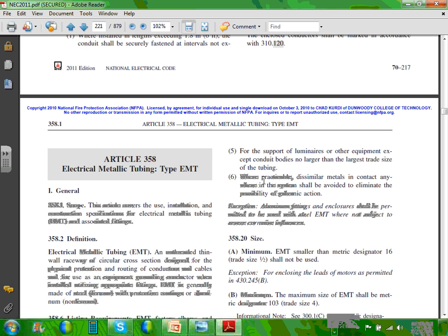I don't want to walk you through each and every one of them, but typically if you pay attention to .10 and .12 and .80, guys, in whatever article, these are uses permitted, uses not permitted, and the ampacity. I said there's close to 50 wiring methods in this code, guys. You're going to be using them as needed, dipping in. If you were sitting for a master exam, we go deeper into where to find things, but when we test for masters and journeymen, we give you the code book.